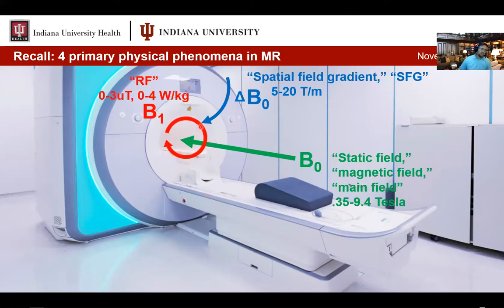Of course, there's the RF field, which occurs in the bore, as we talked about in my first talk. The good thing about the RF fields and the time-varying magnetic field gradients is they are primarily constrained to the RF bore. These are measured when you use the B1 plus RMS metric in microtesla. 0 to 3 microtesla is a common range. Or if you're talking about absorbed energy, you can look at the rate of absorbed energy in a body, and that's typically 0 to 4 watts per kilogram. We refer to this as B1. So when we talk about the RF field, we usually talk about this as B1.